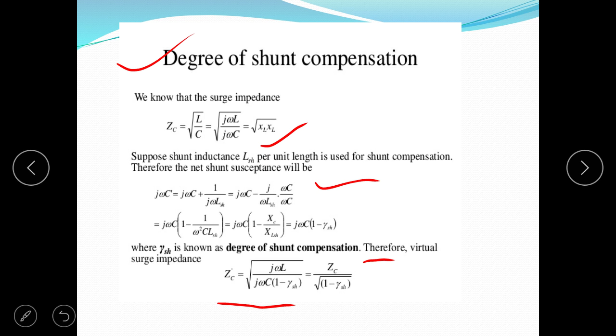So we know that due to series or capacitive compensation, reactance of the transmission line decreases, due to which power transfer capability of the transmission line increases, voltage profile improves, and stability of the line increases. But due to shunt compensation, impedance of the transmission line increases, but shunt compensation is essential to reduce the Ferranti effect in some cases. This is the compensation of transmission line.